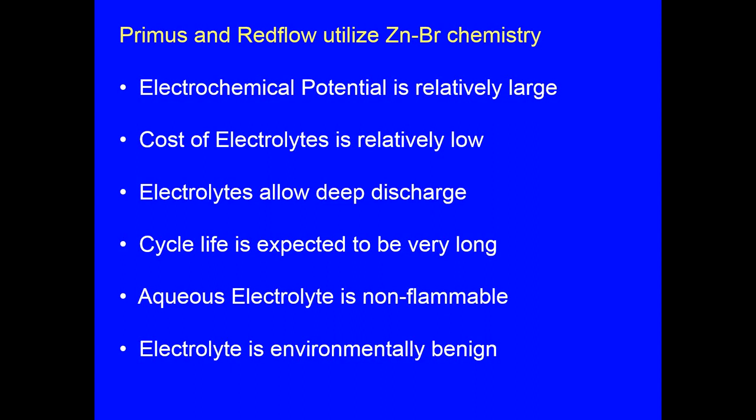Both Primus and Redflow utilize zinc-bromine chemistry. This creates a flow battery, but not a redox battery as such. Advantages of zinc-bromine include: the electrochemical potential is relatively large — more than vanadium-vanadium actually. The cost of electrolytes is relatively low because zinc and bromine are fairly common. The electrolytes allow deep discharge. The cycle life is expected to be very long; essentially these things can be cycled again and again indefinitely. And because it's an aqueous electrolyte, the system is non-flammable and the electrolyte is also environmentally benign.